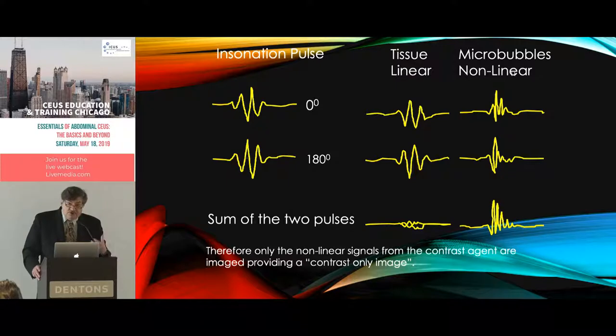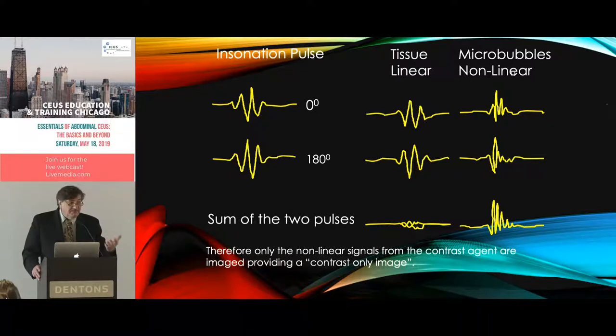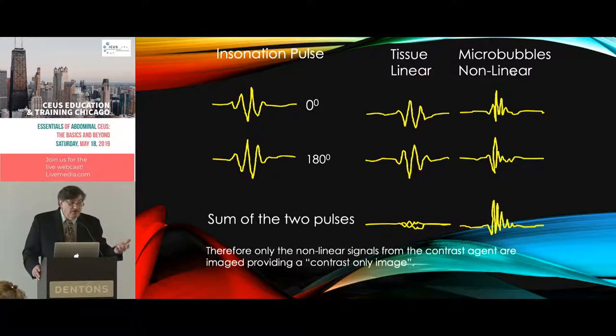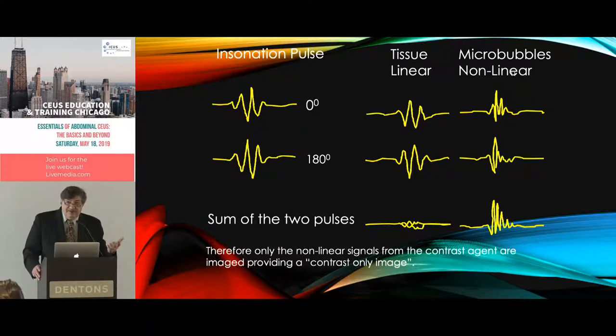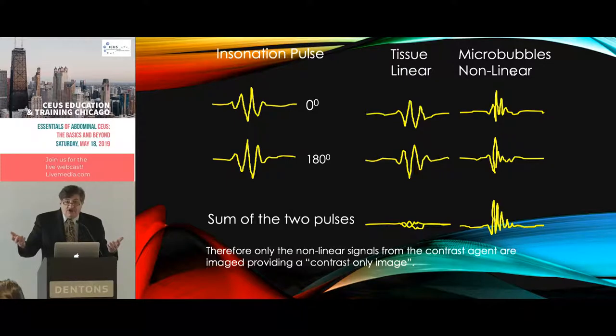We can also subtract the linear responses so that when added together we get our B-mode image back. So we can have both a real-time B-mode image — not quite as good as our standard B-mode, but enough to flag where a lesion is and know exactly where you're at — and our contrast-only image at the same time. We get the best of both worlds.